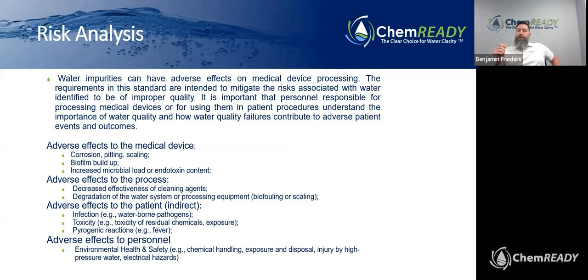So that moves us to the risk analysis. Most facilities should start this step to identify what it is that they need to do to be compliant with ST108. The reason that we are doing this risk analysis is that the whole point of the standard is that water impurities can lead to surgical site infections. The whole reason that AAMI developed the standard is to minimize the possibility of surgical site infections because of medical devices. They have recognized that impurities on those medical devices can have adverse effects. Some of those adverse effects to the medical devices and the process itself could include corrosion, pitting, and scaling. Could have biofilm buildup, increased microbial load or endotoxin content.